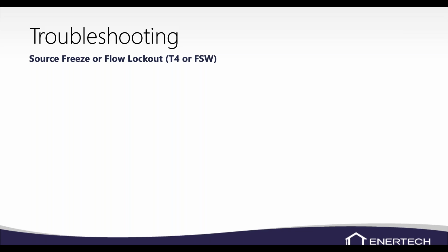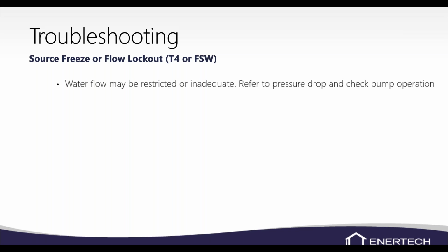Anything with a braze plate will have a flow switch, but it could have a T4 sensor as well. The braze plate manufacturers require us to put a flow switch, a paddle switch, in the water line anytime we're using a braze plate. So obviously water flow is restricted. Look at your pressure drop. You could have flow going in the wrong direction.